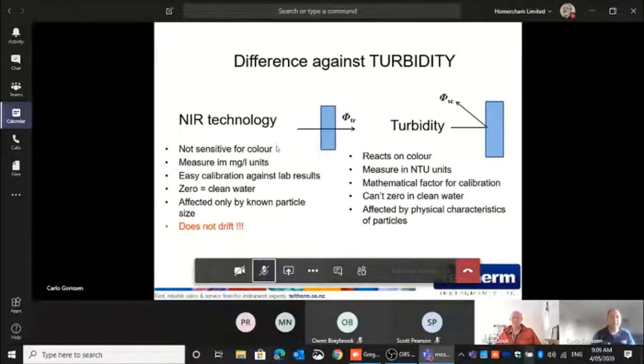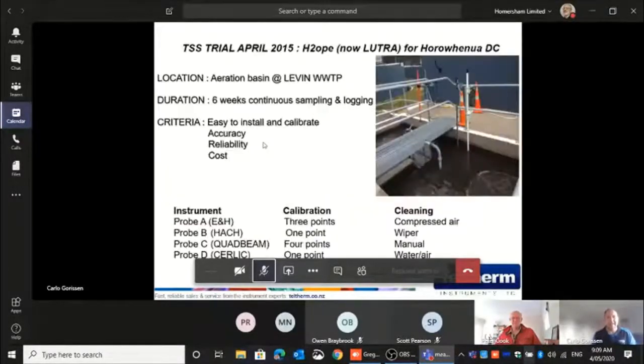It's only affected by particle size for us, not the physical characteristics of the particles. Of course, if you do scattering, if you got a round particle or a square or a triangle, it changes it. And the main advantage against turbidity is our sensors do not drift. So basically, once we install them and you do a calibration, you don't really need to touch them anymore calibration-wise. People still trial it and test it. Now, of course, when we told everybody that, nobody believed us. So in 2015, Horowhenua District Council did a trial for the TSS sensors in an aeration basin in Levin.